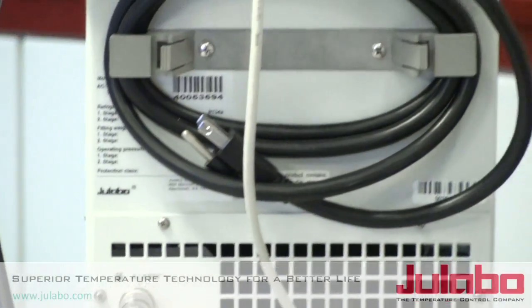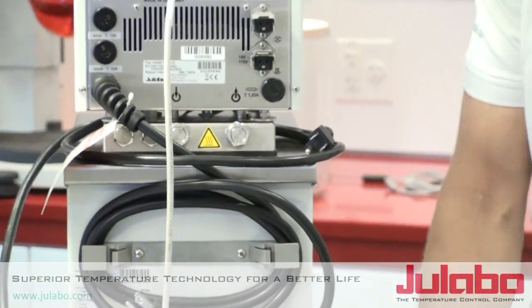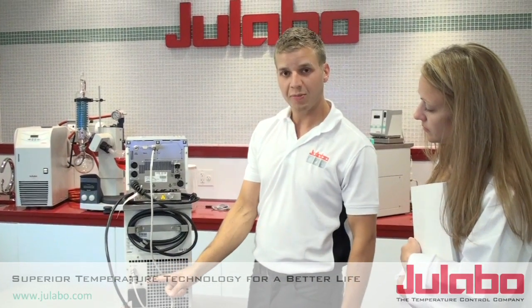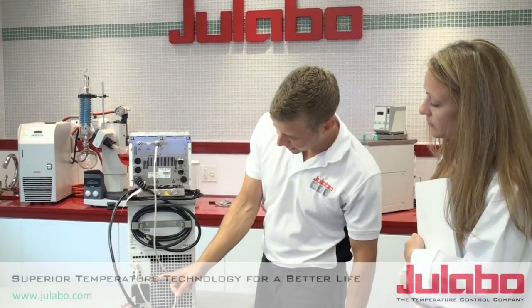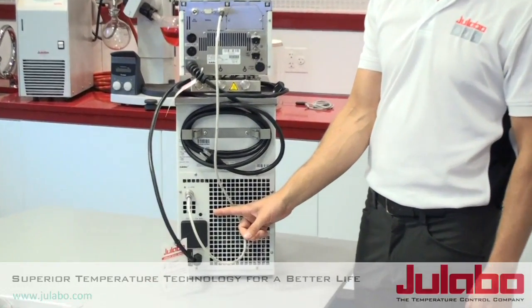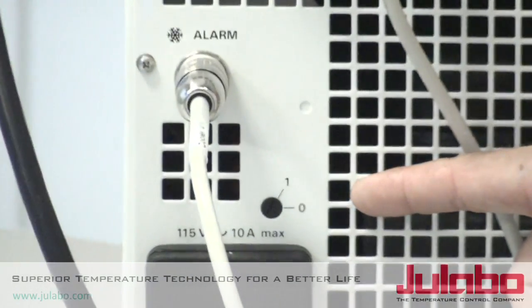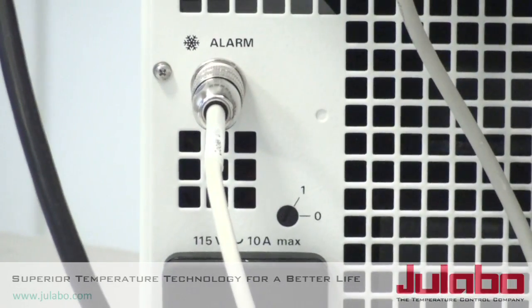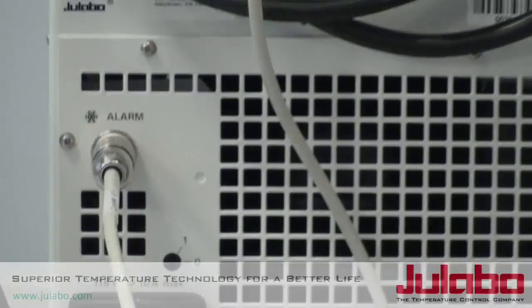Now note, if you have an Economy Series Julabo unit this procedure will be a little bit different. You will see here on the back of the unit that there is a marking for a zero-to-one switch, and that will initiate your cooling compressor communication with the circulator. If you have any issues be sure to call Julabo service.